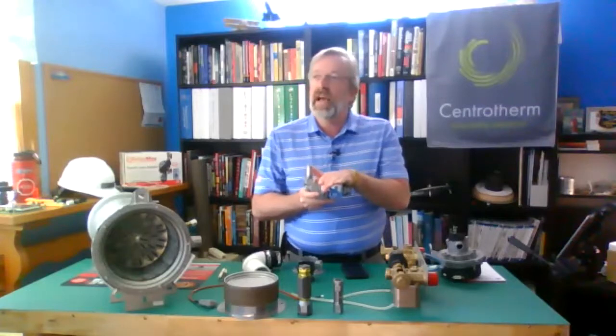If I'm sitting there at my 8 inches, I open up my gas valve, I do my thing, I go 8 inches to 6 inches. I got pressure, got pretty good volume, keep moving. What happens if I go sitting at 8 inches, tell it to spark, tell it to do its thing, and 8 inches stays 8 inches? Well, now I want to find out why, because that's telling me my gas valve did not open.